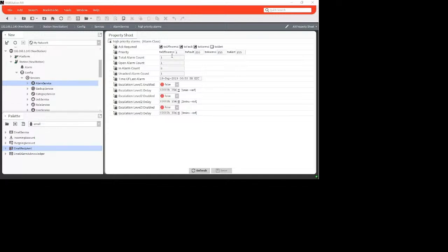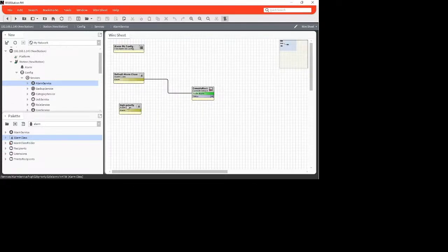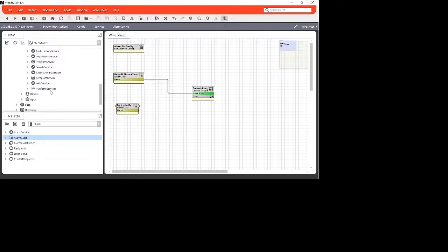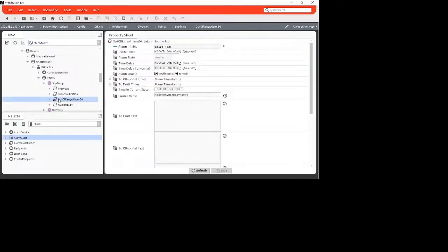And that you want to have some high priority alarm, you head down to this drivers and drag that over. IO. Here is how you can then, in your alarm extension, scroll down and you would see the class here. You can change it from the default class to making a high priority. So now this alarm becomes a high priority when it goes in alarm.